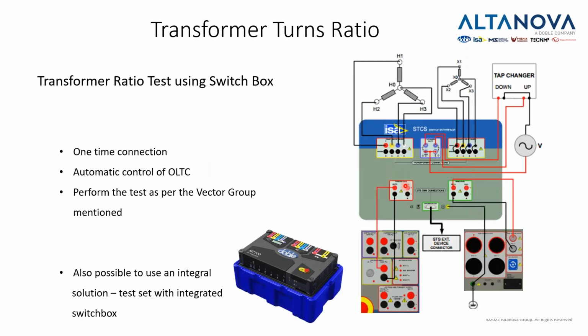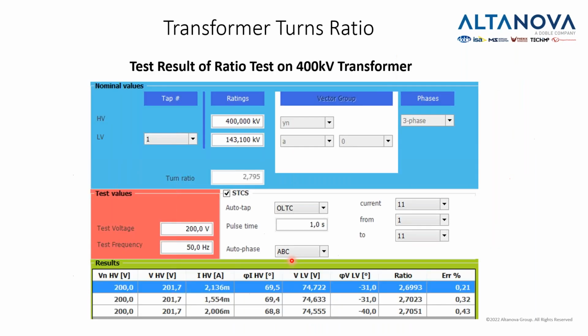In order to do the test, it is very helpful if you can have a switch box. So in this case, with the STCS, for example, we have a switch box which needs to be connected to the device, but the M7100, for example, will have an integrated switch box, and this is a much faster way to do the test, because this can also control the position of your tap changer, and it can also switch phases between each other, and that way you can obtain results much quicker.